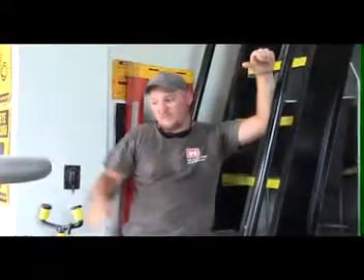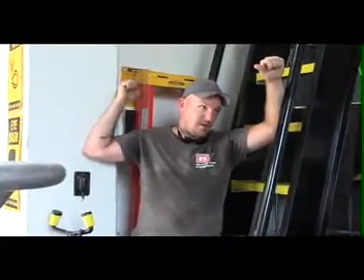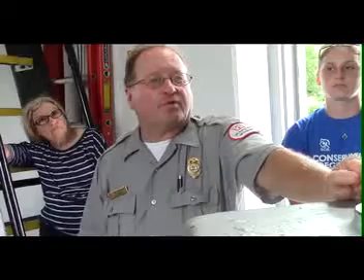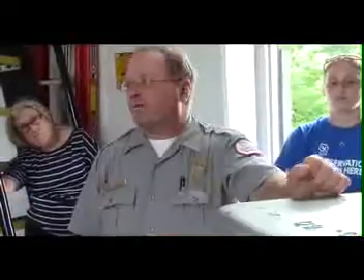There's got to be a massive influx of water because the spillway is 25 feet lower than the top of the dam. We cycle all these gates once a month. Cycle them, grease them, and inspect them. All 6 gates. They're monitored and taken care of 365 days a year, 24/7. Everybody's subject to be called in at any time. All dams leak. Even the Hoover Dam leaks somewhere. You never get them sealed completely.